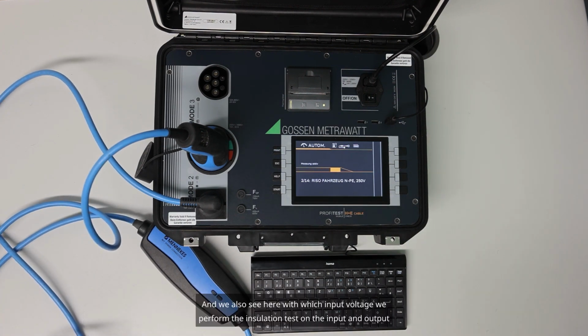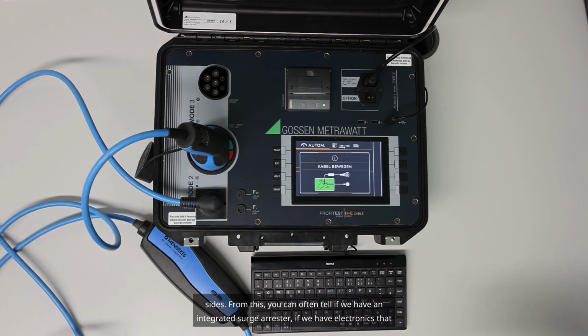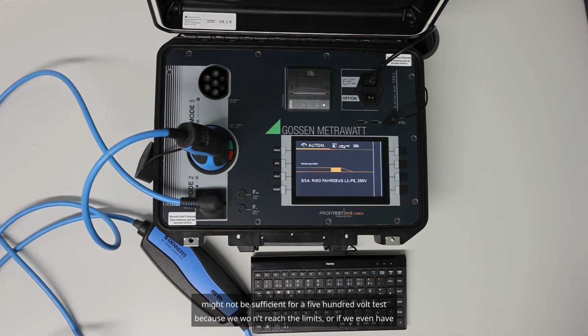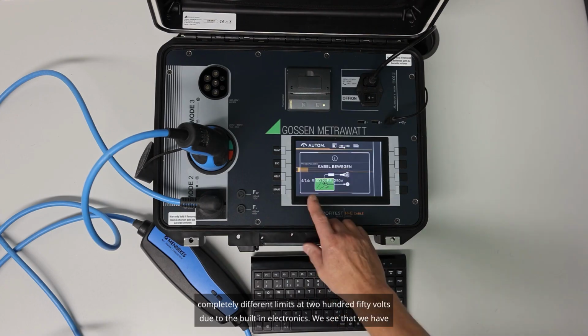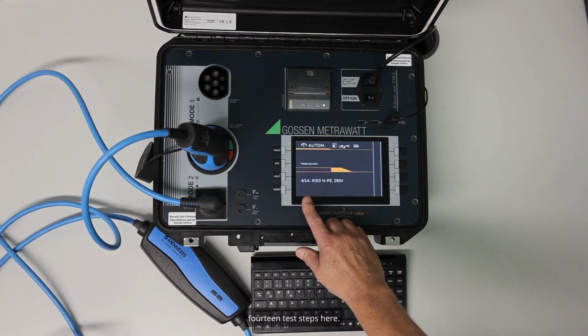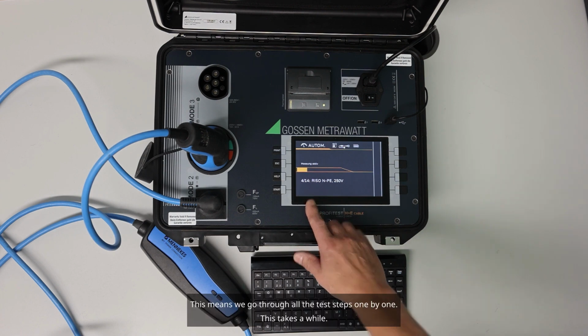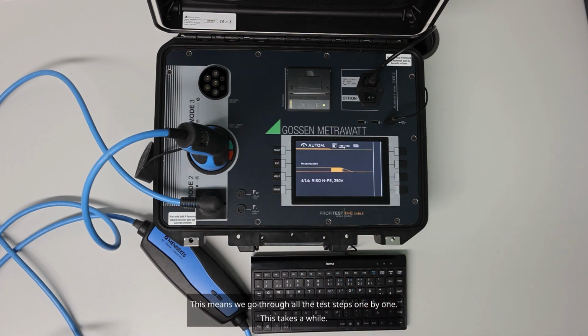And we also see here with which input voltage we perform the insulation test on the input and output sides. From this, you can often tell if we have an integrated surge arrestor, if we have electronics that might not be sufficient for a 500-volt test because we won't reach the limits, or if we even have completely different limits at 250 volts due to the built-in electronics. We see that we have 14 test steps here. This means we go through all the test steps one by one. This takes a while.